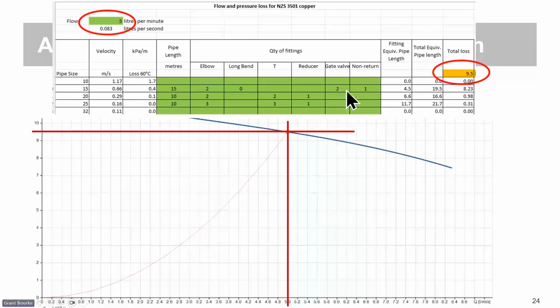So the last step that we want to do is check this velocity, that the velocity in our ring main return pipe is going to be under 1 metre a second, and we've got 0.7 or so metres per second of velocity, so we're good to go. Now, what I would generally do is go through and check that with my probable simultaneous demands applied to my supply pipes, that I put those flow rates in my supply pipes into the flow at the top, and just check down this velocity column to make sure that I hadn't exceeded those supply flow rates in my pipes. But we can see here that for our return pipe, we're good to go at 5 litres a minute.